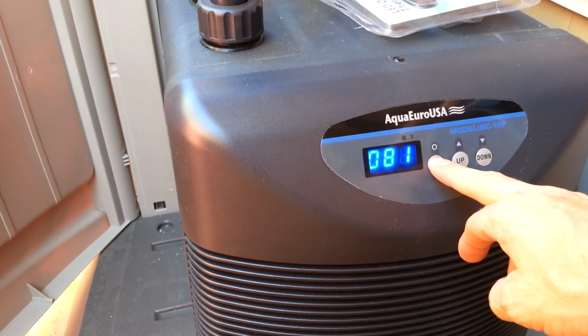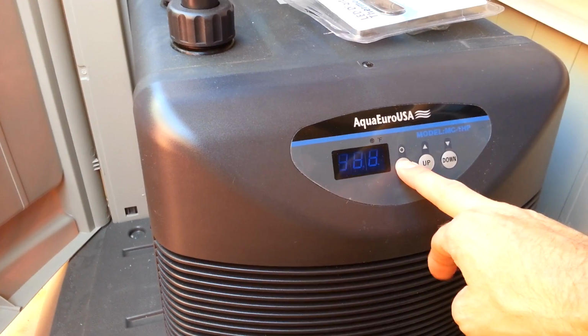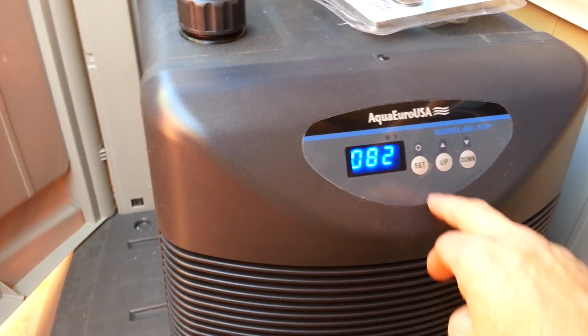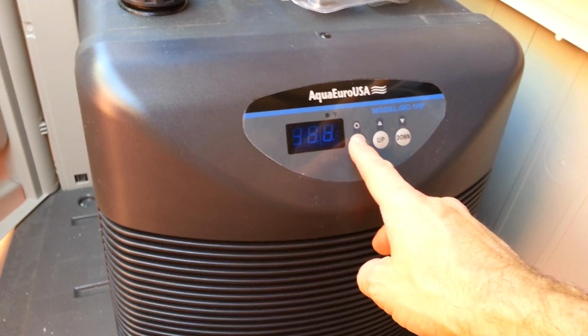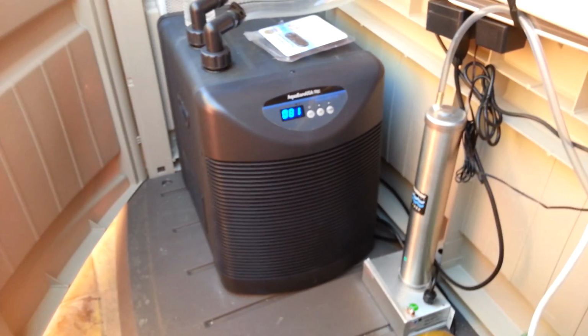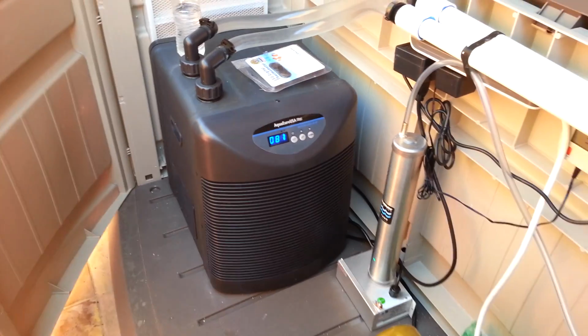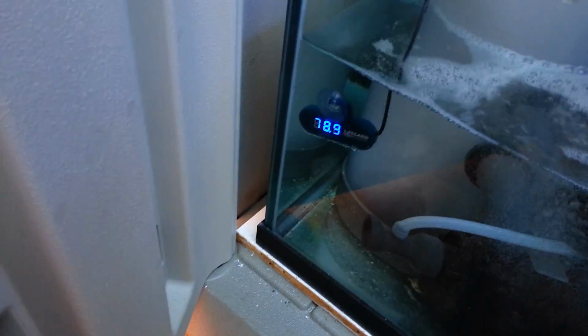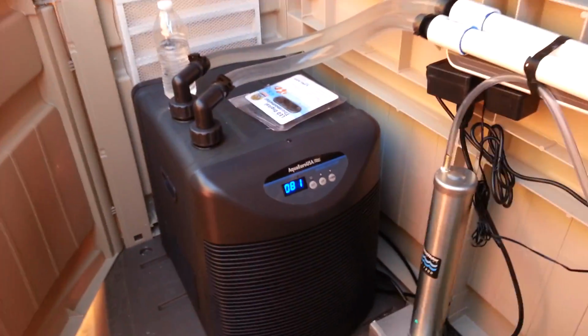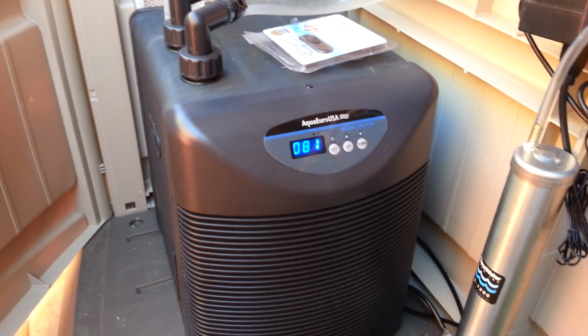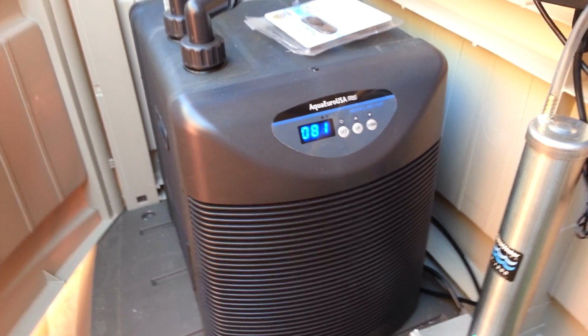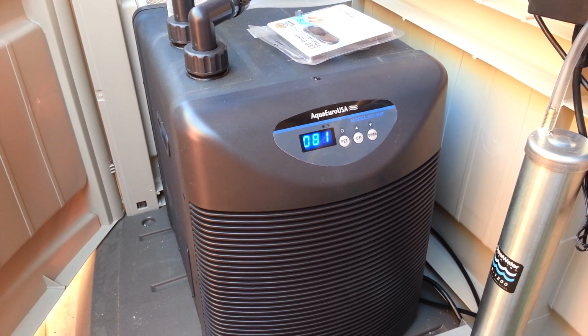So here's what I'm going to do. I'm going to shut the chiller off by making the set point back up to 82. That way we can shut it off, but we'll keep water running through it, see what happens. Okay, there, the chiller's gone off. The pump pumping water through the chiller is still running. Still got the same temperature there, so we know we're good in the sump. So we have water pumping through from the sump. The chiller isn't running.